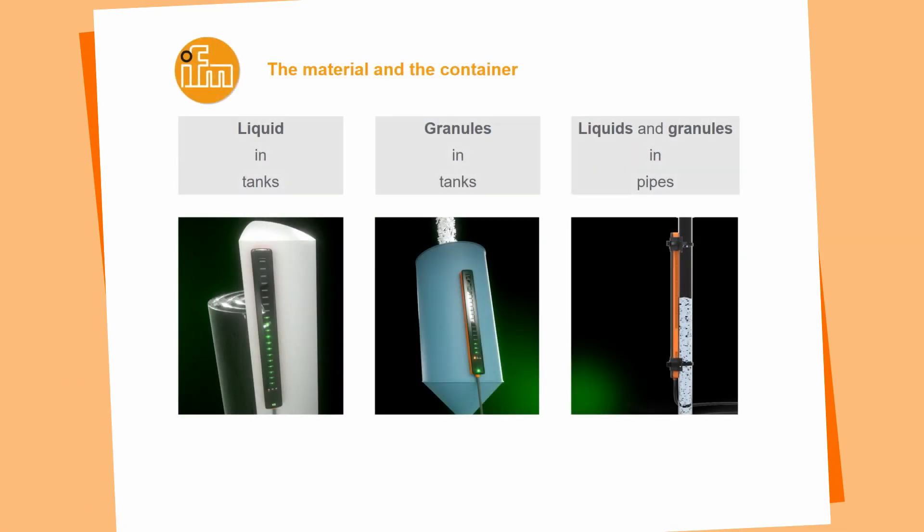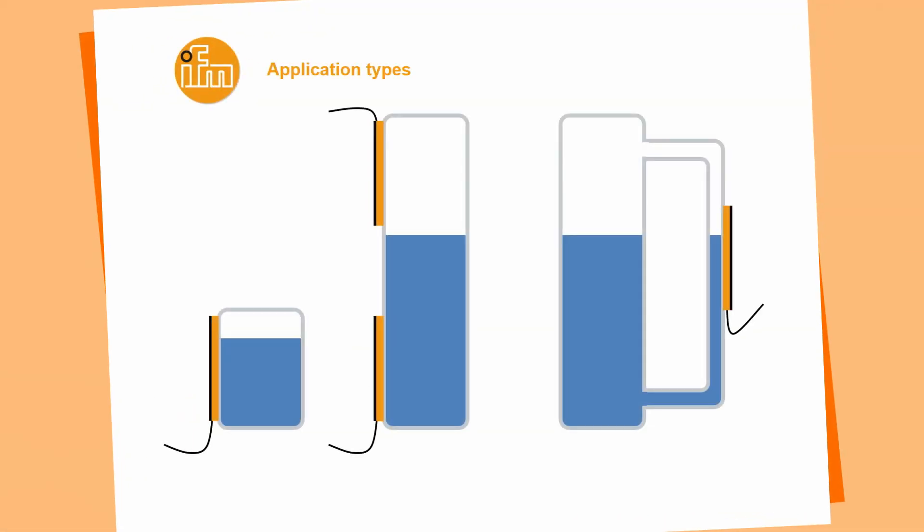We can use the KQ10 in several applications. One is detecting liquid inside of a tank. The other one is detecting granules in a tank and we are able to detect liquid or granules or whatever inside of a pipe or bypass or sight glass. Please beware that the container, the tank wall is out of a non-conductive material, for example not out of metal. We can also use the sensor in very small tanks, for example in printers and we are able to detect or to measure the complete value of the tank.